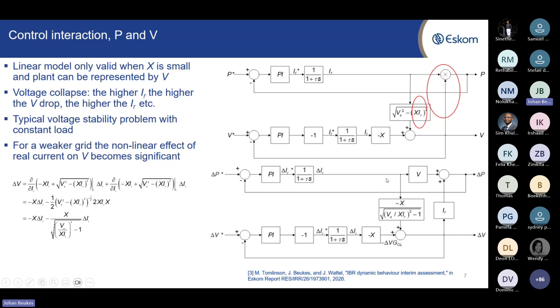Let's look at the time delay, the second issue. If you remember control systems from varsity, when you look at the root locus, you can see that a time delay in a control system—typical in inverter control where signals need to be transported from one system to another—gives zeros on the open loop on the right-hand side of the complex plane, which end up as closed loop poles on the right-hand side of the complex plane. If your system gain becomes too high, you end up on the wrong side of the complex plane, making it an unstable system because you have negative damping.